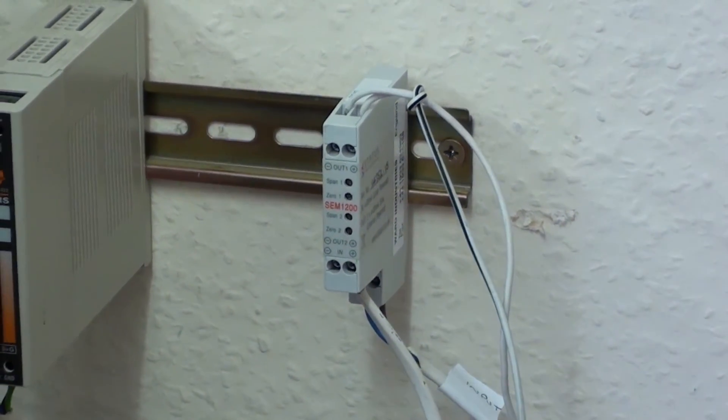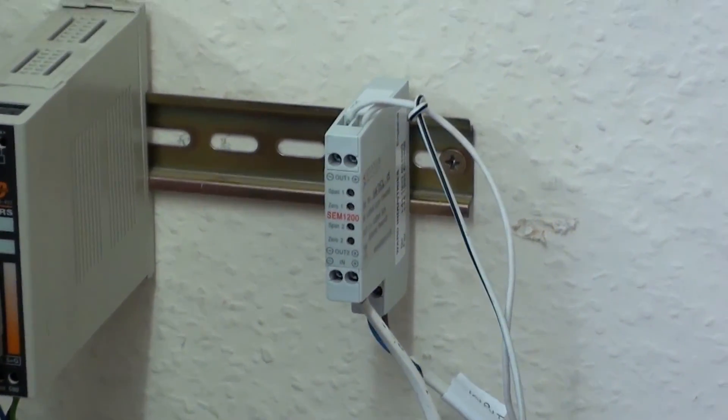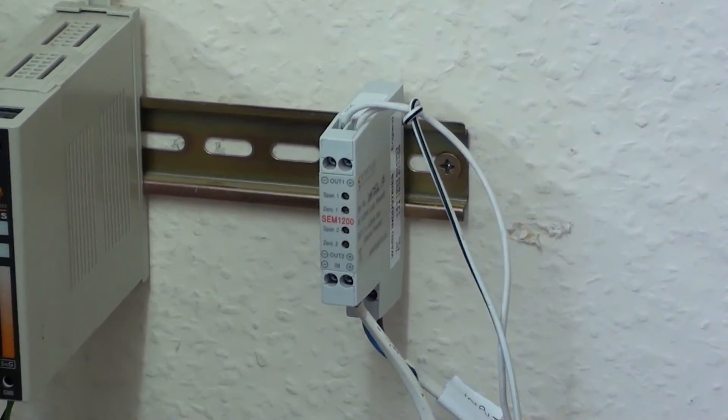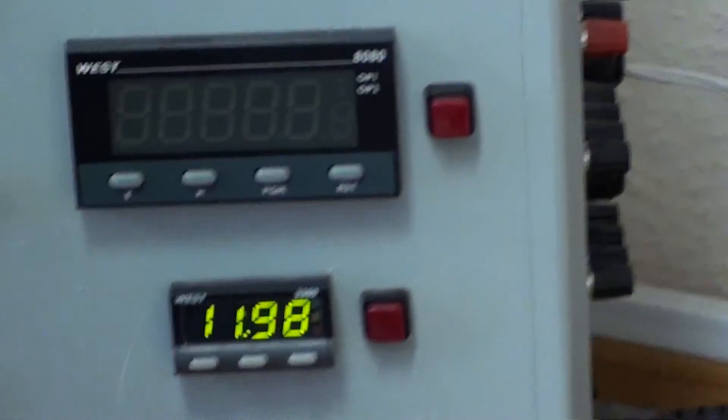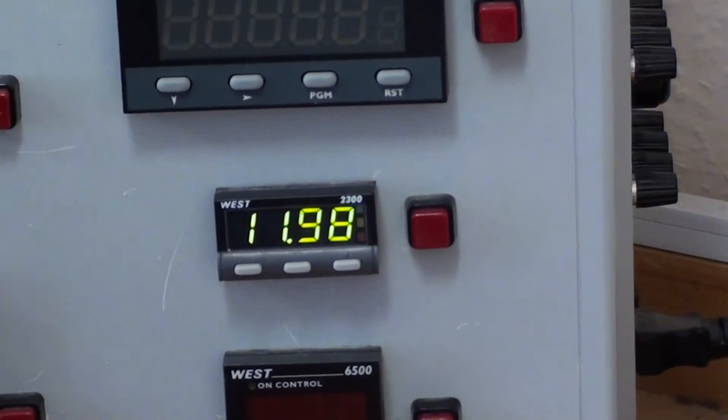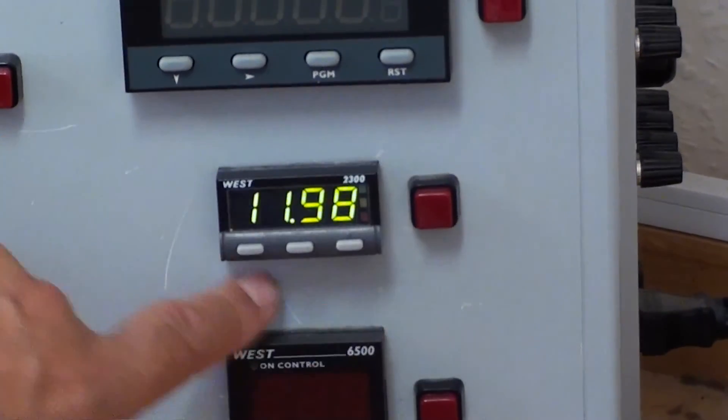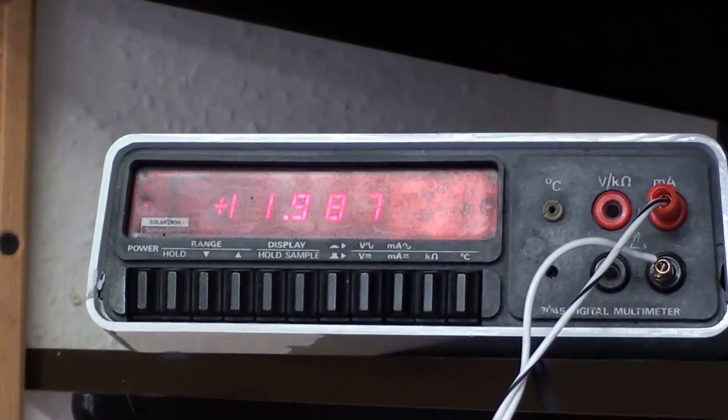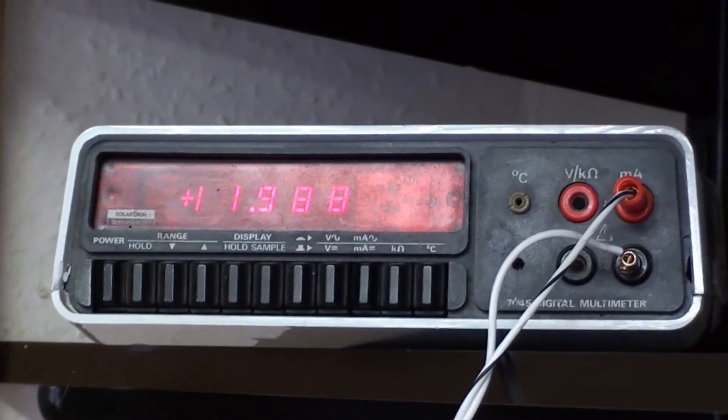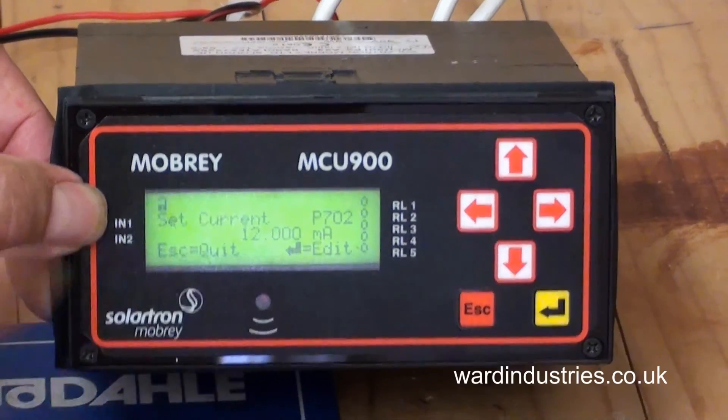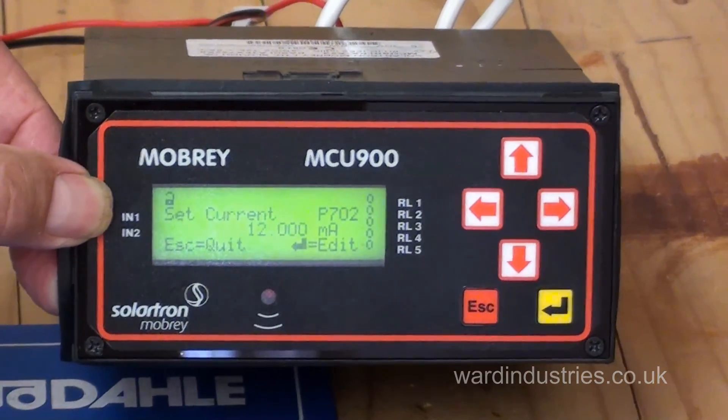That gives a 4 to 20 milliamp output signal, isolated output signal to two loops, but those loops must be externally powered, typically with a 24V power supply. Here we can see one digital indicator and the value on the multimeter, two output signals, and it's the same value of the input signal that's being transmitted by this control unit.